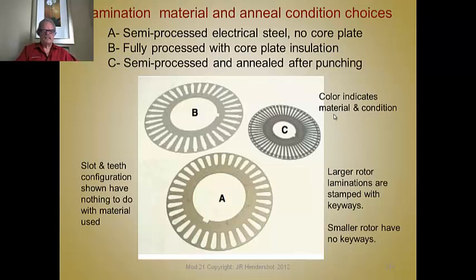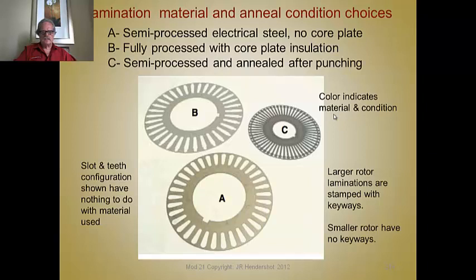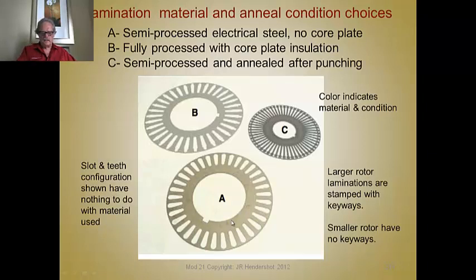Lamination material: whatever applies to stators applies to rotors — semi-processed steel with no core plate, or fully processed with core plate, and semi-processed with core plate annealed after punching, as long as you use a core plate that doesn't burn off when you anneal it, and the C5 core plate does that. As you can see here, the color of these indicates which one was which. Some larger machines have keyways in the bore and smaller machines don't — they just shrink them right onto the shaft.